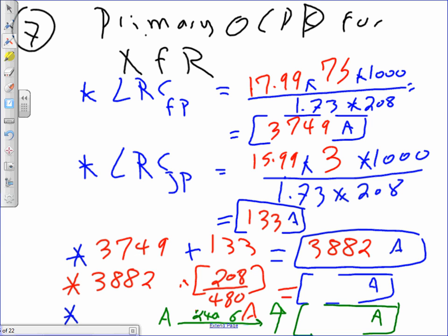Take it to the next level. Now with the 3,882, we're going to multiply by the voltage ratio. Everybody understand what we're doing? We multiply by the voltage ratio because we're looking at the primary. We have to multiply by the voltage ratio like we said the other day. That will drop it down to 1682. Matt, do you see how beautiful that is, when you raise the voltage, how much you went from almost 4,000 amps down to 1,600 amps just by raising the voltage. Okay, now you go to the primary side, 1682. Take it to 240.6, guys, and that will get you a healthy 2 gauge.